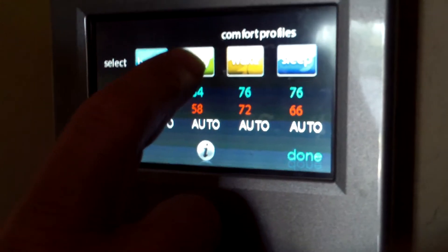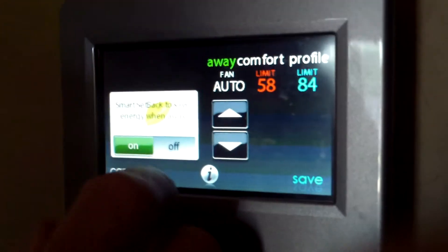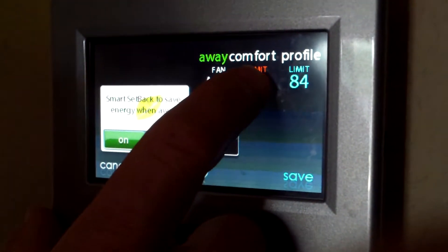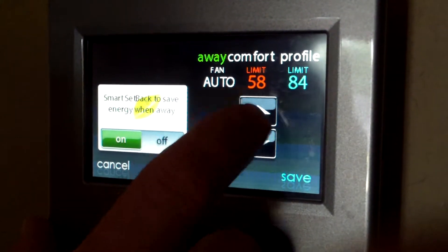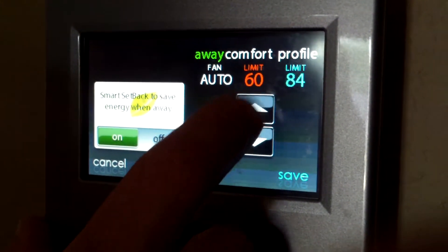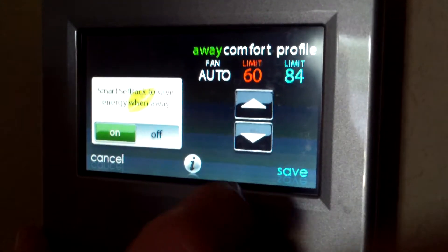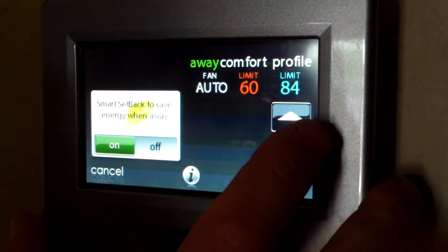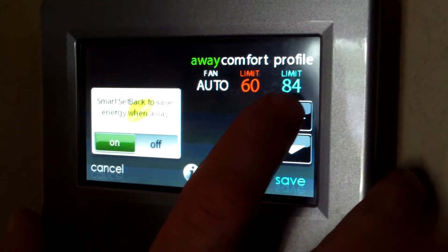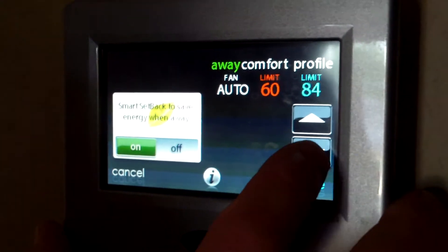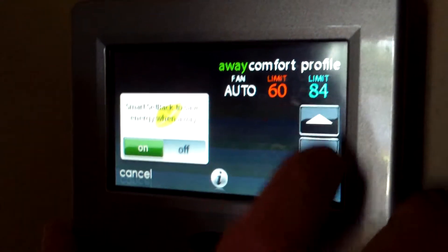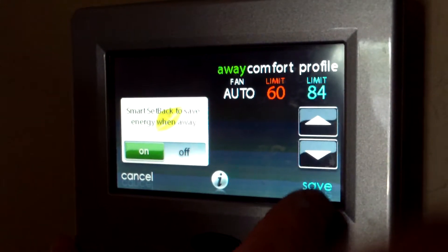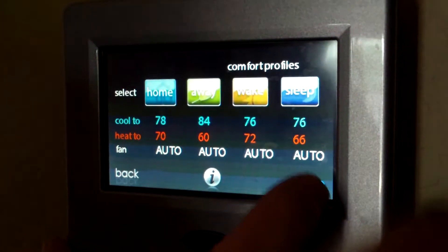Next, I go to the Away setting — this is for when I'm out of the home. I don't want the heat to come on unless it goes below 60. I don't want the air to come on unless it goes above 84. I hit Save.